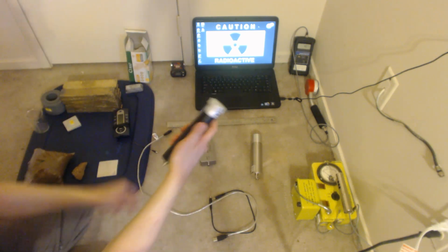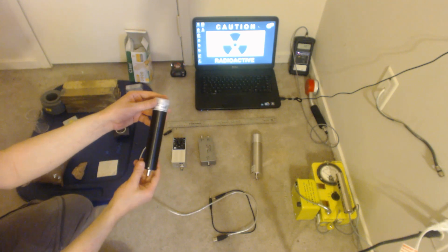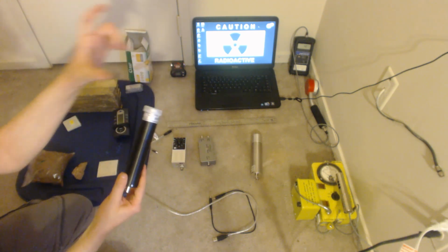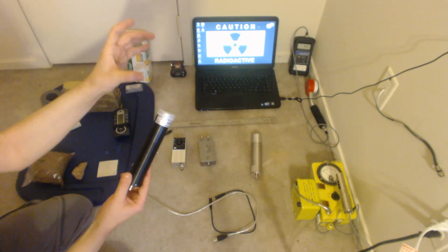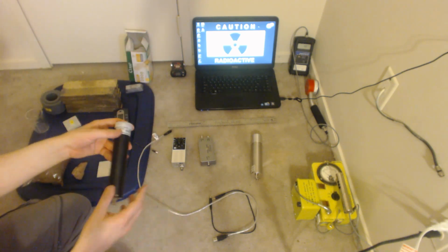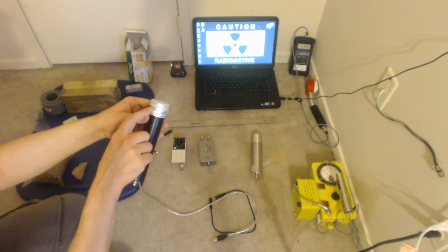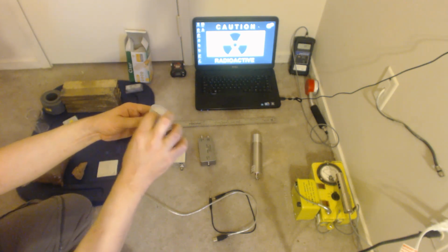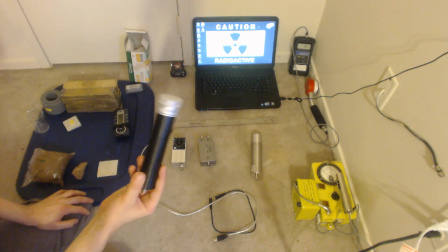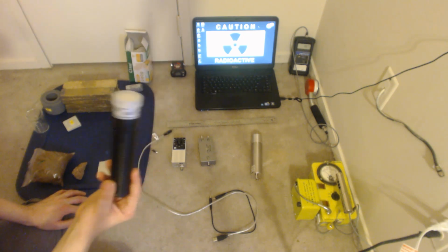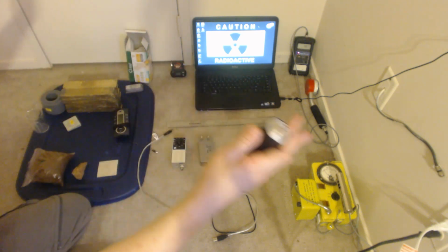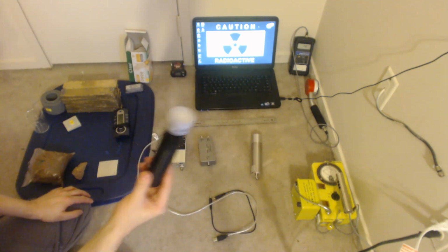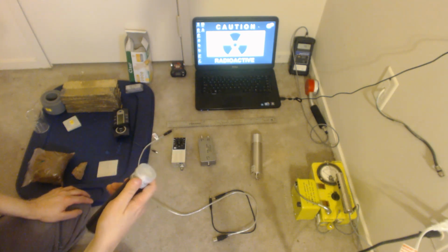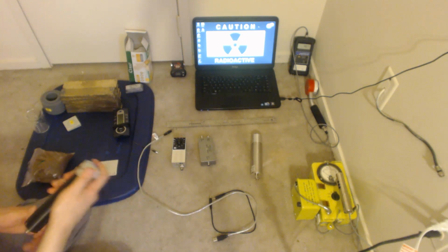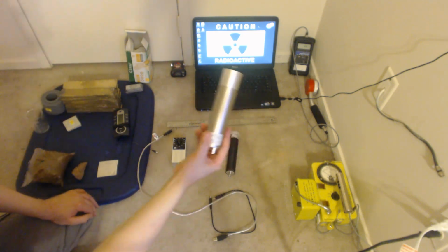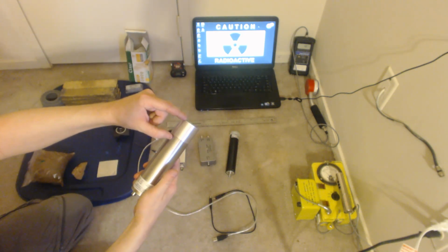Same works with the crystal. This is a thin crystal probe, and that's not indicative of cesium iodide probes. That's indicative of this specific model. You can get a big fat cesium iodide crystal. You can get a big one, no problem. And if you did, that would be great. But this particular specific unit is a low energy gamma probe. It's a little tiny thin crystal. It's like a few millimeters thick. That's wonderful for low energy X-rays. But it is terrible for broad ranges that you'd want to look at normally. So this is a beautiful probe for things like XRF, and if you don't know what XRF is, you probably don't want to get into it anyway. I can explain if you're interested. This guy, however, has a 1.5 inch crystal. Big thick crystal.